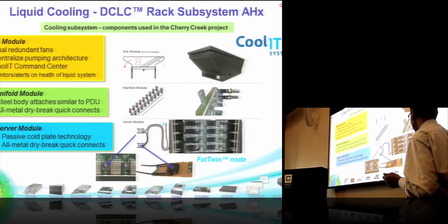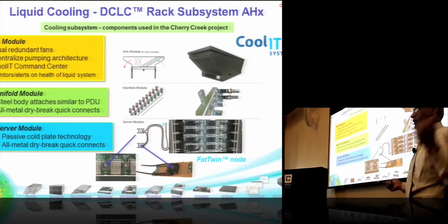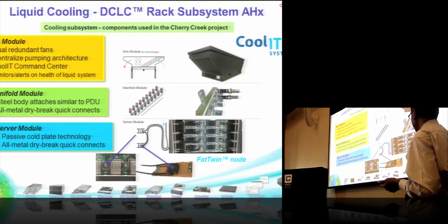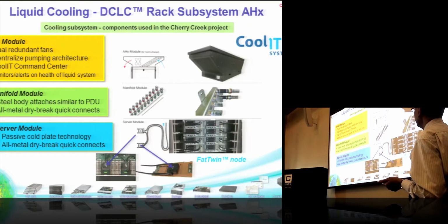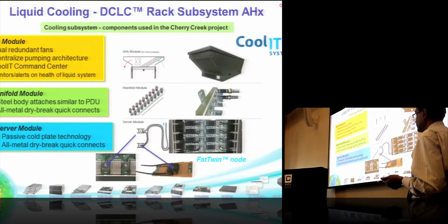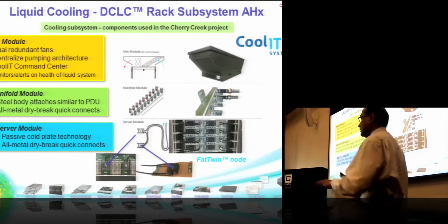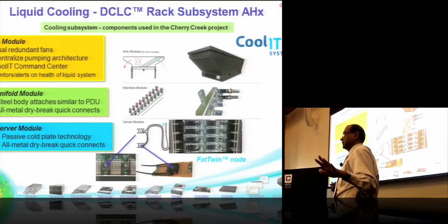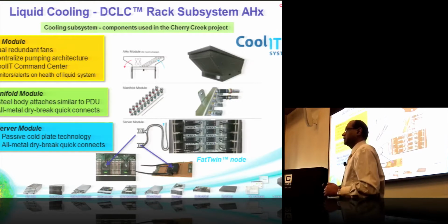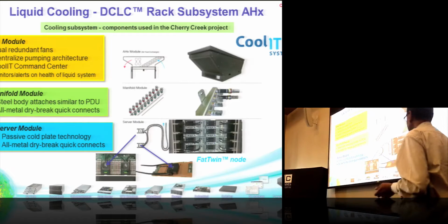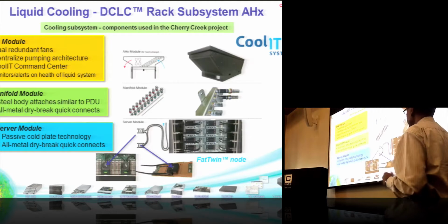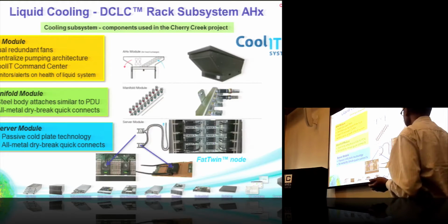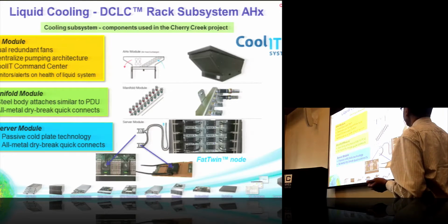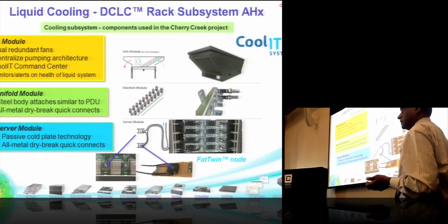You can take a look at it when you go into the exhibit hall. This system is then hooked up to a manifold and then to a heat exchanger. This is a self-contained single rack, there's no other connectivity, everything is self-contained. This is becoming pretty popular, and there is redundancy built into the centralized pump, because that's probably your biggest failure point.